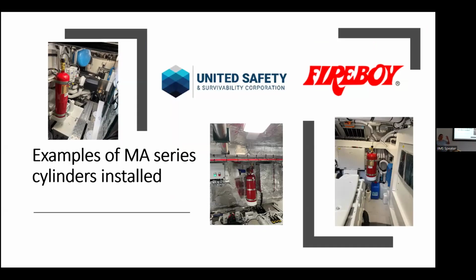Maximum distance from the ceiling. So you want the extinguisher higher rather than lower. So maximum distance from the top bulkhead, it's 24 inches. If it's too low, the gas is heavier, so it will fall down as it discharges. No obstruction is important, especially with FK, because it's stored as a liquid. So you want to have at least 1 meter of a clear space for the discharge, for the gas to get out and spread around the room to do the job.